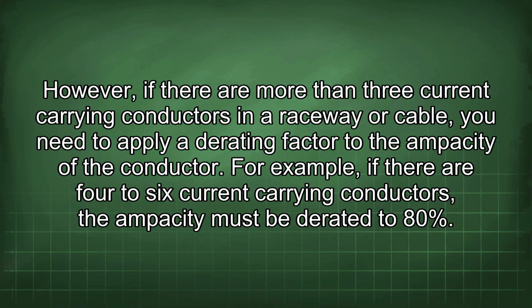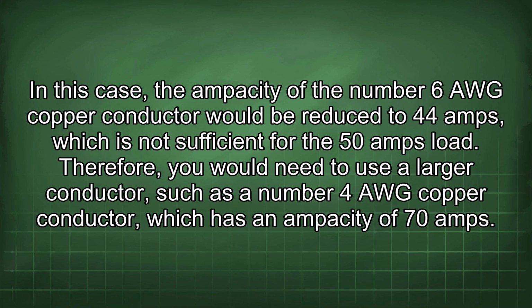However, if there are more than 3 current-carrying conductors in a raceway or cable, you need to apply a derating factor to the ampacity of the conductor. For example, if there are 4 to 6 current-carrying conductors, the ampacity must be derated to 80%. In this case, the ampacity of the number 6 AWG copper conductor would be reduced to 44 amps, which is not sufficient for the 50 amp load.